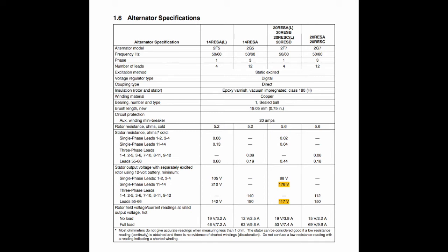So that alternator, with these specifications, with that separate excitation, there is not an issue. So if we had an output issue, it would be in the voltage regulator in the controller. With that, you'd have to go to the wiring diagram and measure and ohm out your FN and FP leads going back from the P2 connector on the back of your RDC2 controller to your brush block, and the wiring there, and ohm that all out. And check your parameters and settings in the controller. If they all check out, it possibly could be a controller voltage regulator issue. Thank you and have a nice day.